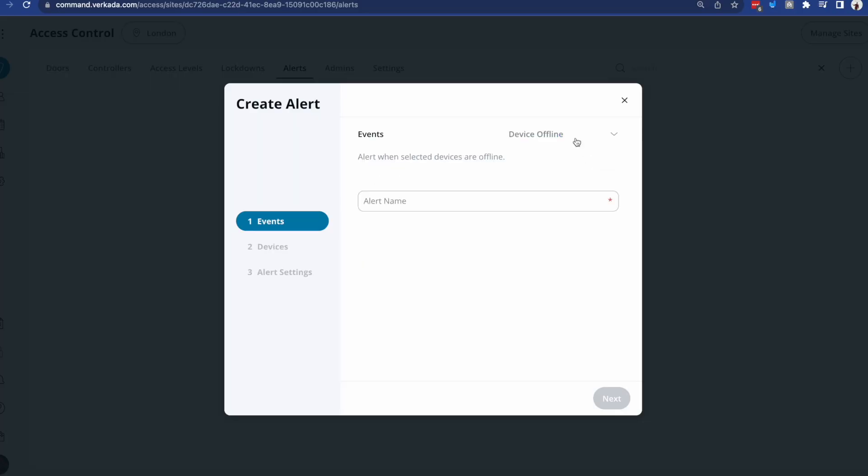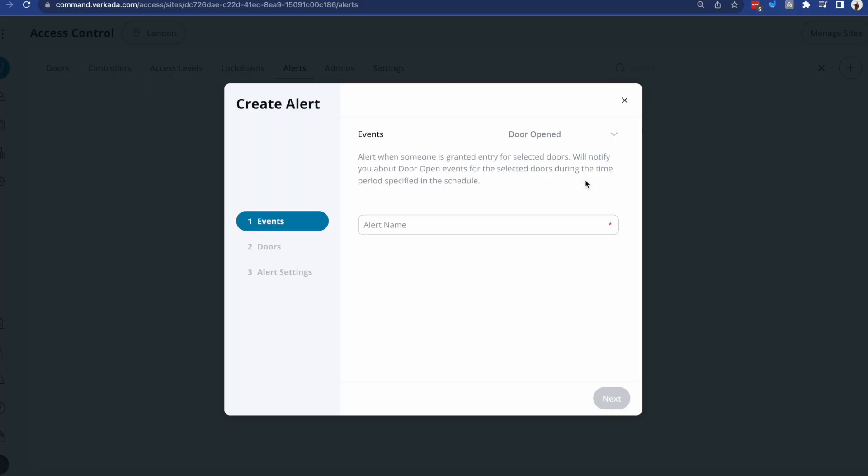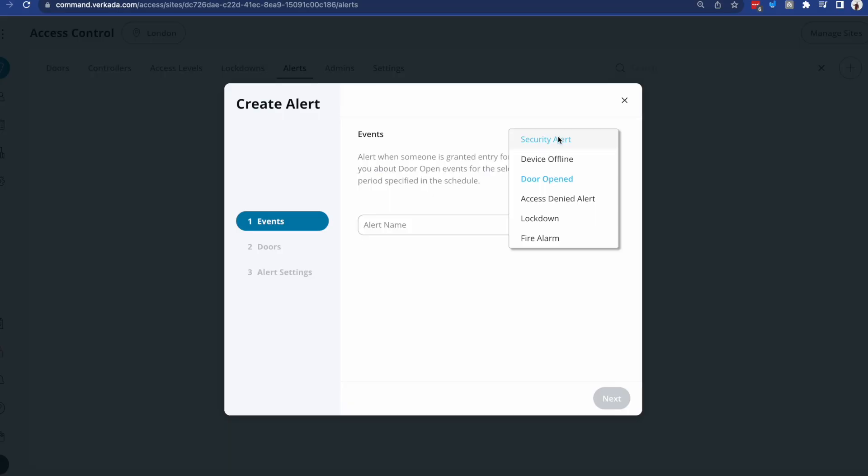A device offline, quite self-explanatory. A door open, this is what we call a suspicious entry alert when you still allow people to get in, but you do get a notification. Think about something like somebody's coming into the office after hours or in a certain more secure area. Access denied, lockdown, and fire alarm. So this is where if you have a fire relay and you have your fire alarm system linked together with access control, we're actually able to report and alert anytime that fire alarm goes on.